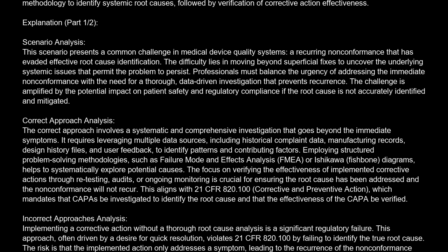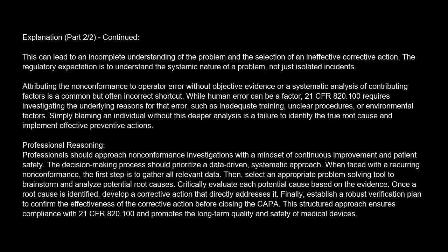Focusing solely on the most recent occurrence of the nonconformance, without considering historical data or trends, represents a failure to conduct a comprehensive investigation as required by 21 CFR 820.100. This can lead to an incomplete understanding of the problem and the selection of an ineffective corrective action. The regulatory expectation is to understand the systemic nature of a problem, not just isolated incidents.